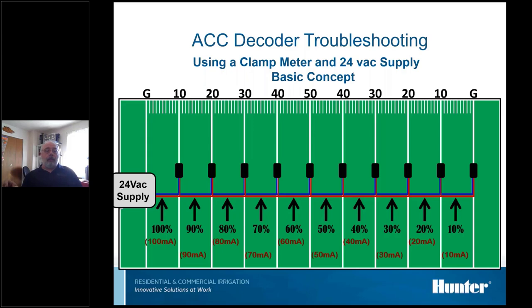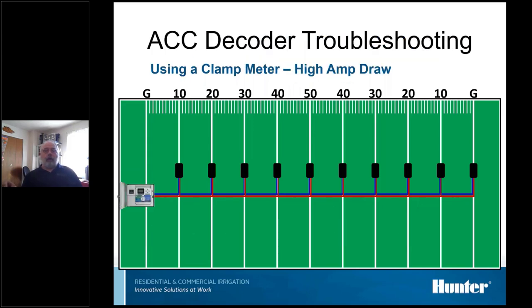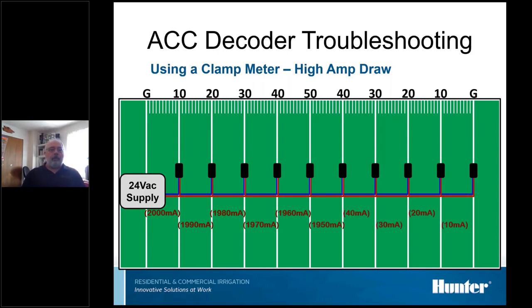So when you have a problem and you're drawing high current, the controller's probably turning itself off, so we're going to hook the transformer up and get a reading. Again, I wouldn't check every spot, but if you did, these are the numbers you would see. We got 2,000 milliamps, or 2 amps, at the controller. That's quite a bit. So now you can just go out and see what we're looking for.